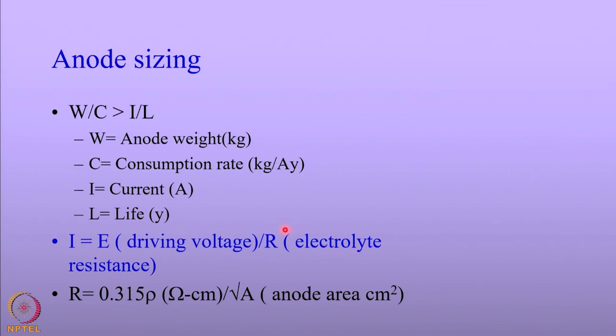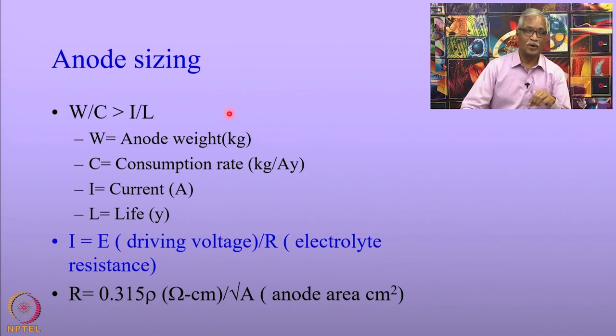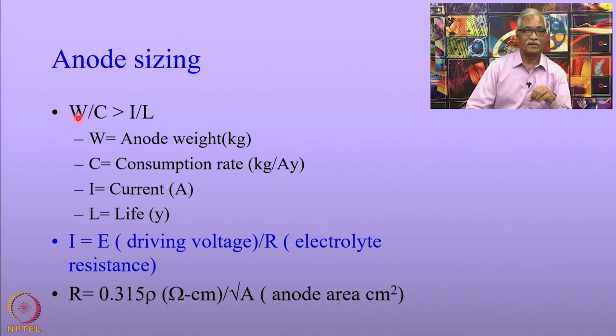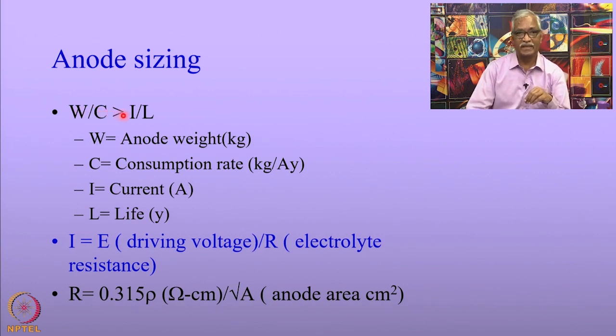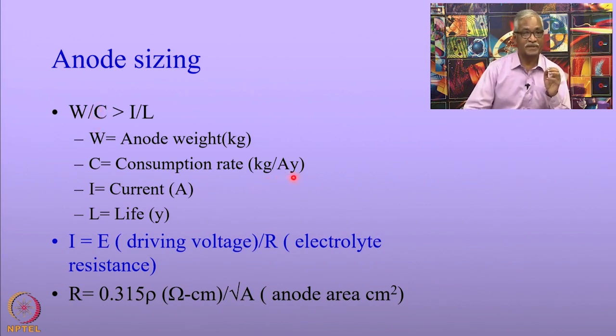Sizing of the anodes is very important when using sacrificial anodes. The anode weight required for cathodic protection is calculated based on the equation W/C ≥ I/L, where W is the anode weight, C is the current consumption rate in kg per ampere-year, I is the current required to protect the structure, and L is the life of the structure. This decides what the anode size should be in terms of weight.